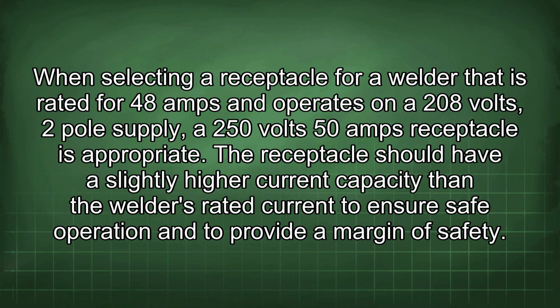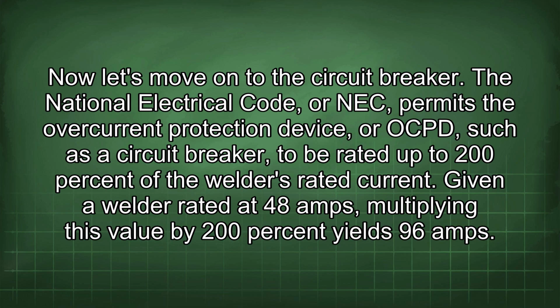When selecting a receptacle for a welder that is rated for 48 amps and operates on a 208 volts 2-pole supply, a 250 volts 50 amps receptacle is appropriate. The receptacle should have a slightly higher current capacity than the welder's rated current to ensure safe operation and to provide a margin of safety. Now let's move on to the circuit breaker.